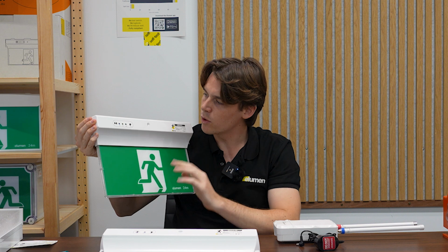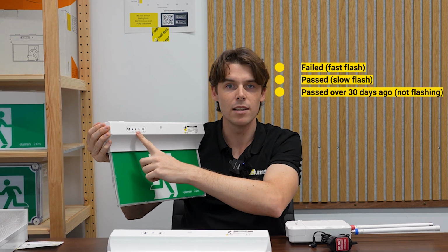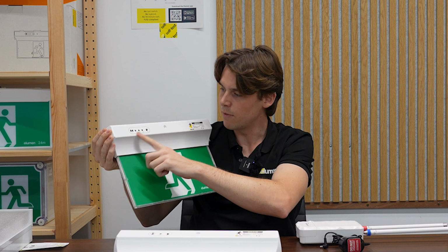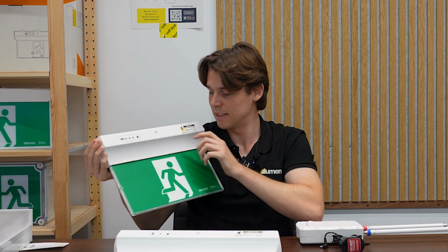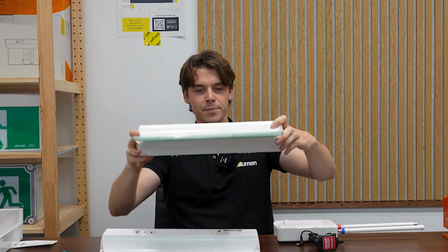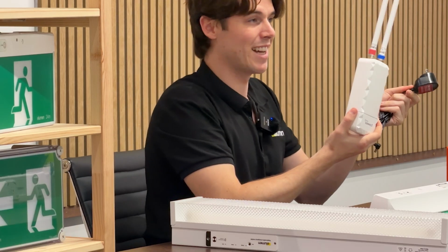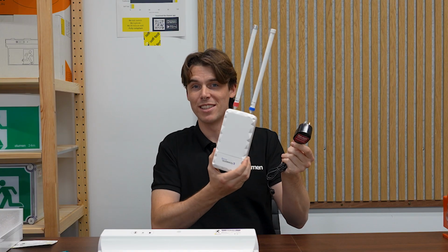Elumen lights also follow the standard for the status light, which is yellow, and there's a blue light as well for networking systems. If it's got these three lights, then you know that you're working with an automated system. And here the sticker says it's self-test. The other way is if you see a gateway on site, that's a dead giveaway that it's a remote monitoring site. This one is for Elumen networking.